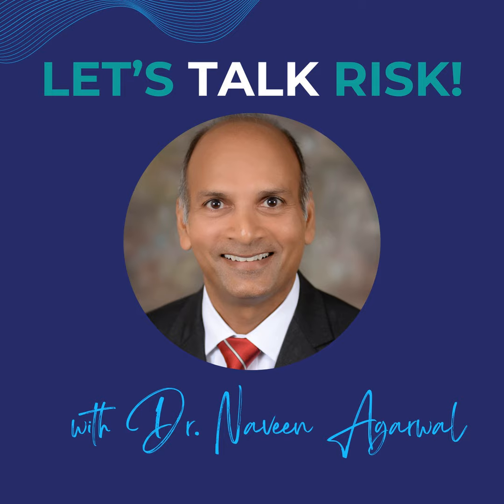And then we went on to all the different documents, the FMEA, the use-related risk analysis. One thing that people lose sight of, I'm afraid, with some of these tools, especially as I look at URRA, is that it looks to be a complete risk analysis in itself, and it becomes a standalone document that doesn't feed into the risk traceability summary.